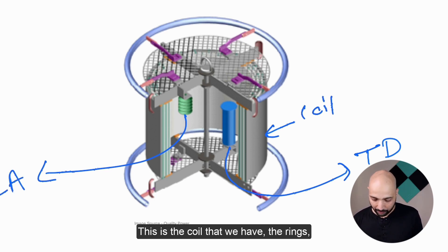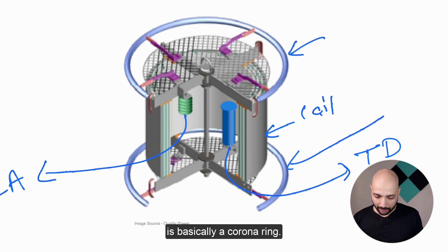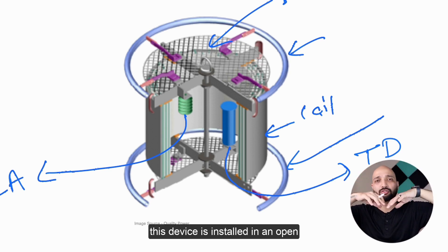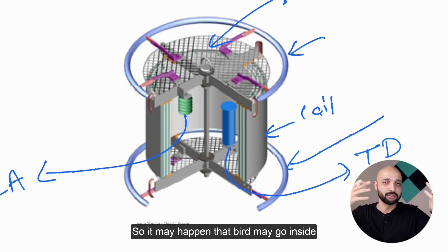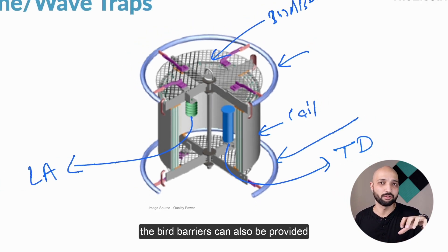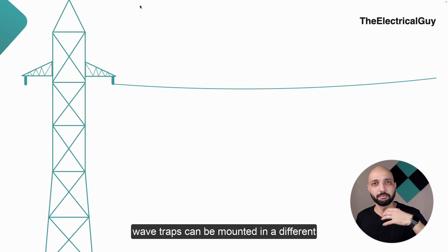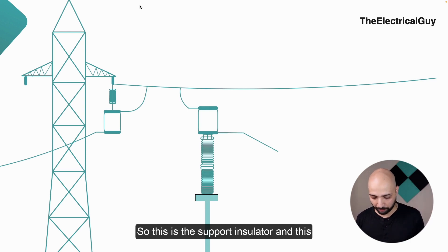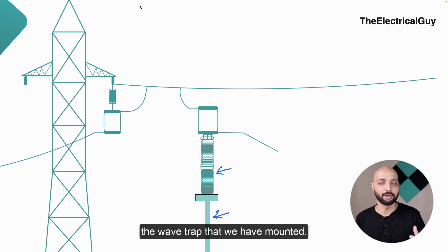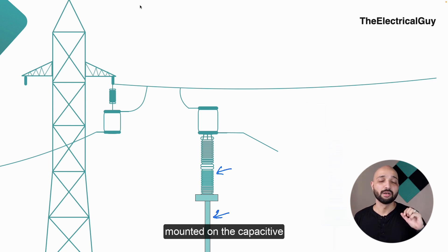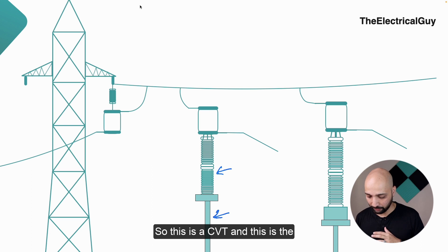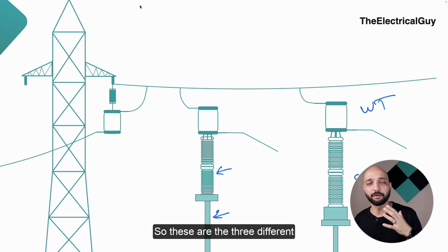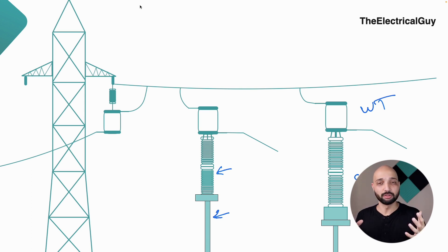The rings visible on the coil are corona rings. Since this device is installed in the open atmosphere and is hollow, bird barriers are also provided to prevent birds from entering. Wave traps can be mounted in different ways: directly on the gantry of the tower, on a dedicated support insulator with a support structure, or directly on a Capacitive Voltage Transformer. Not all substations will have wave traps — only those where power line carrier communication is used.